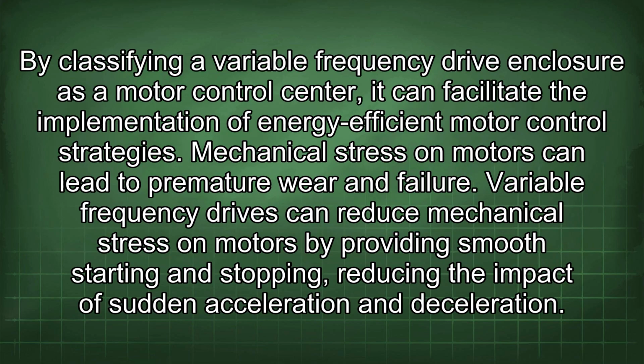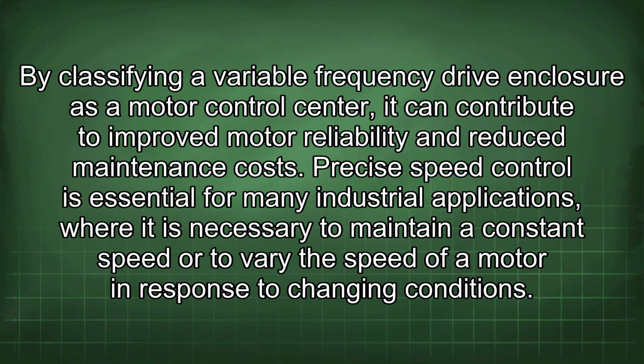By classifying a variable frequency drive enclosure as a motor control center, it can facilitate the implementation of energy-efficient motor control strategies. Mechanical stress on motors can lead to premature wear and failure. Variable frequency drives can reduce mechanical stress on motors by providing smooth starting and stopping, reducing the impact of sudden acceleration and deceleration. By classifying a variable frequency drive enclosure as a motor control center, it can contribute to improved motor reliability and reduce maintenance costs.